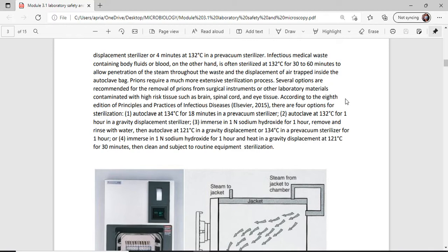are 4 options of sterilization. First, you need to autoclave it at 134 degrees Celsius for 18 minutes in a pre-vacuum sterilizer. Okay, pre-vacuum sterilizer. Then, the other option is autoclave at 132 degrees Celsius for 1 hour in a gravity displacement sterilizer. Okay, 1 hour, gravity displacement sterilizer.